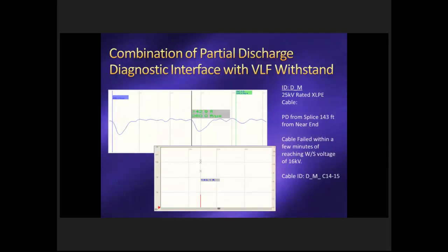Alright, if we look at some actual traces from the field, you can see over here, this is a PD impulse, and this is the second impulse, and the distance from here to here is 143 feet, and that 143 feet is from the far end. This is a 25 kV cable, and so we'll measure a number of these triggers, and we'll build up what we call a mapping diagram over here. We can see each of these X's represents a PD trigger from the same site in the cable. So that's why I mentioned, don't look at the singular events, get a number of hits at the same location. And this was in a splice, 143 foot from the end.